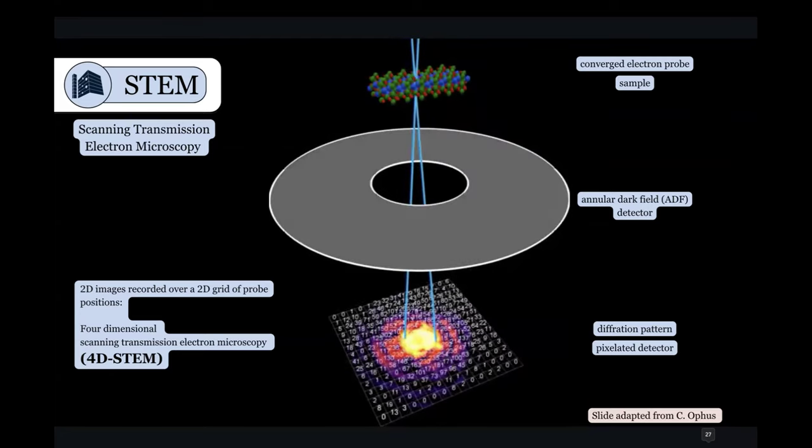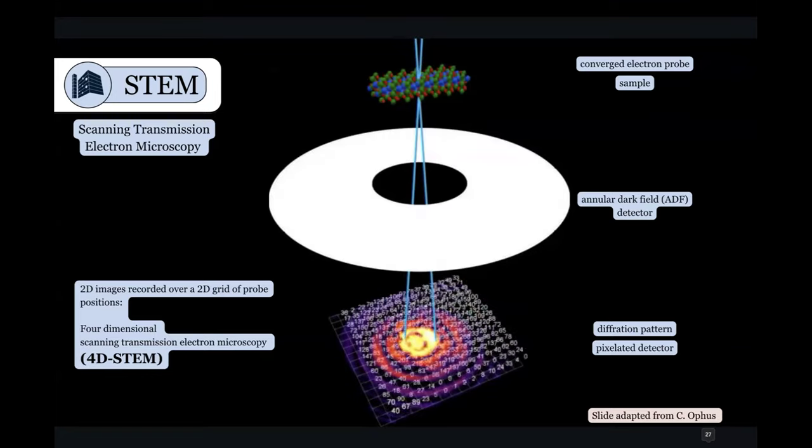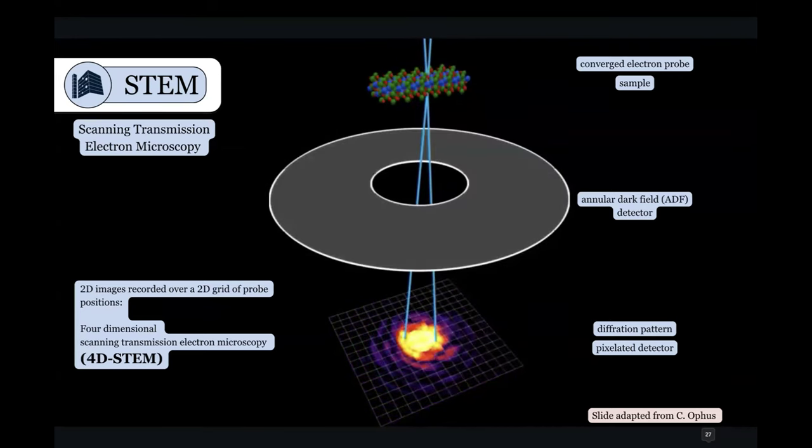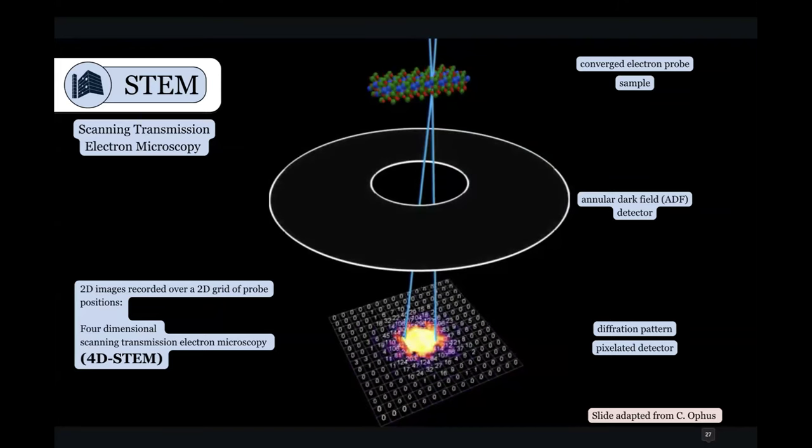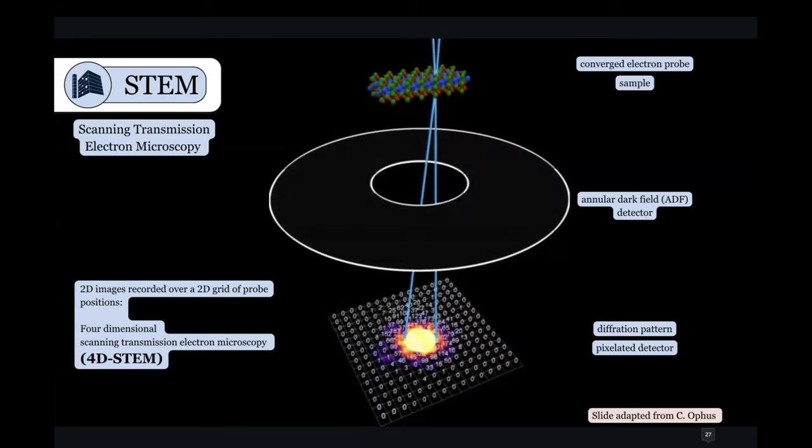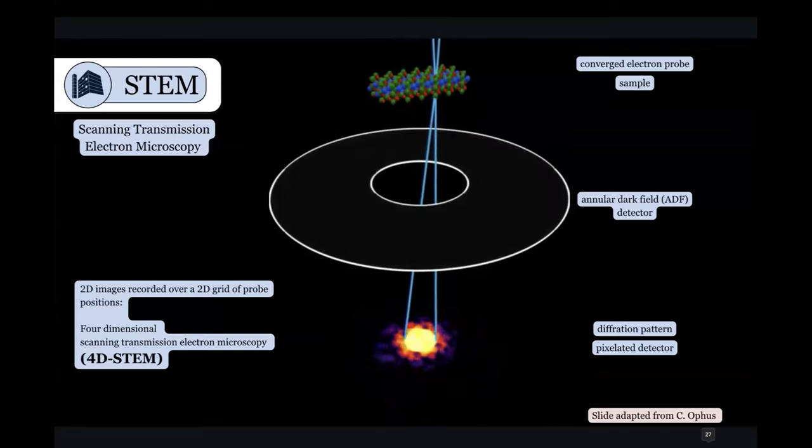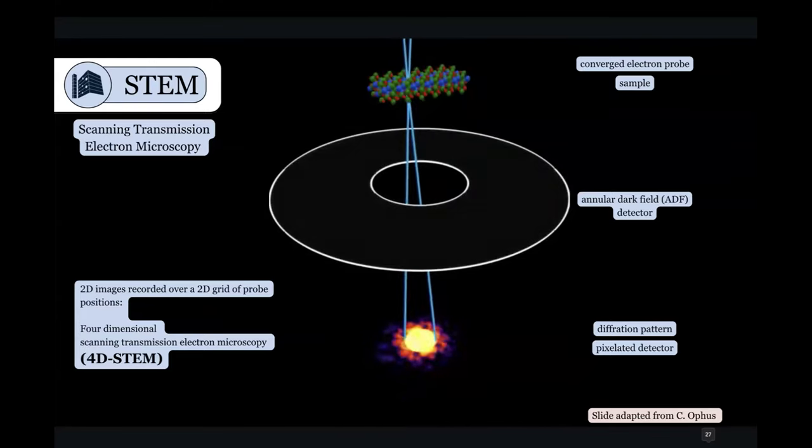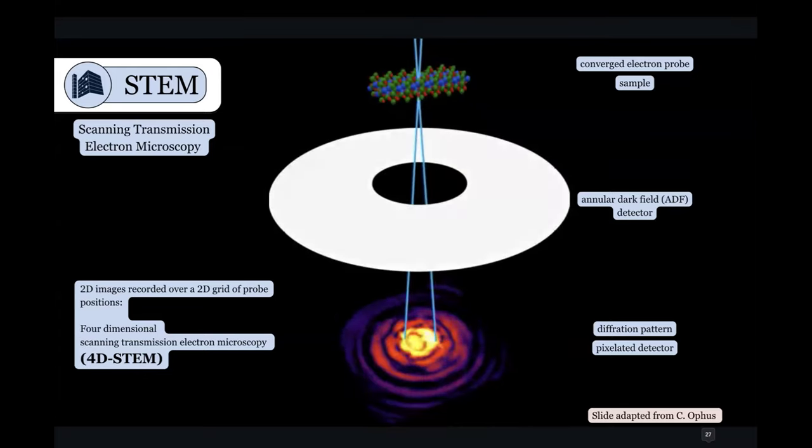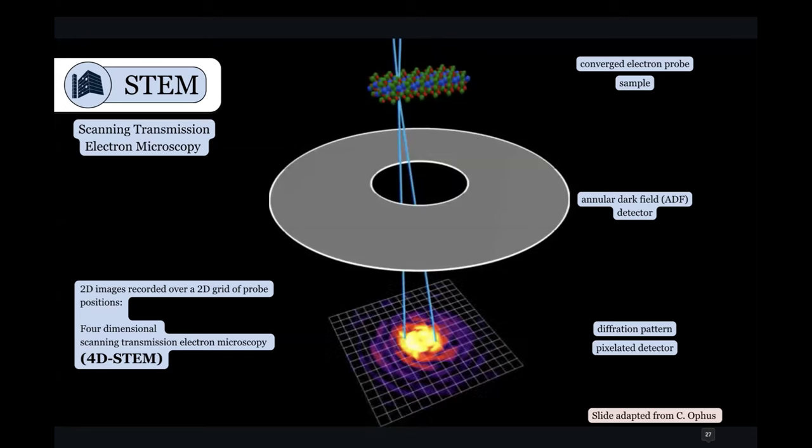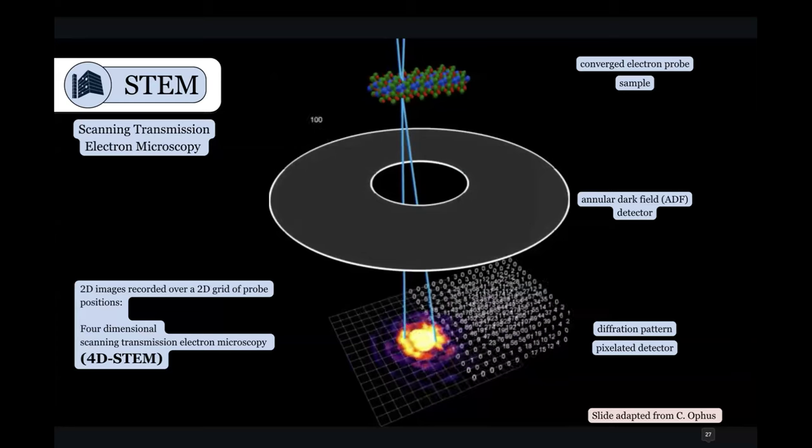And so in kind of the conventional detector technology, one of these detectors that you can put in is called an annular dark field detector. And what that does is at every point along the surface of this sample, you're collecting the scattered electrons that are coming off of the sample around a ring at relatively high angles of scattering. And when you hit one particular probe position, you collect all of them, and you get one piece of information. That's how many electrons hit that detector at that probe position.